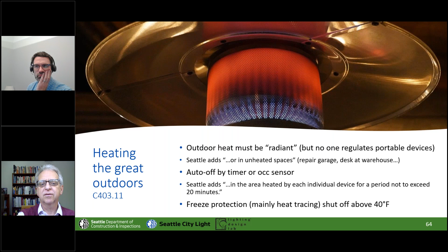It's got to be either turned off by a timer or by an occupancy sensor that's set for 20 minutes. And finally, you can do freeze protection for specific equipment and piping that is set so that it always shuts off at 40 degrees temperature.